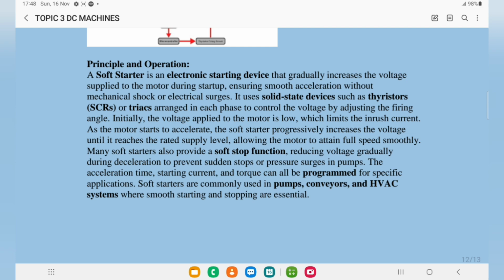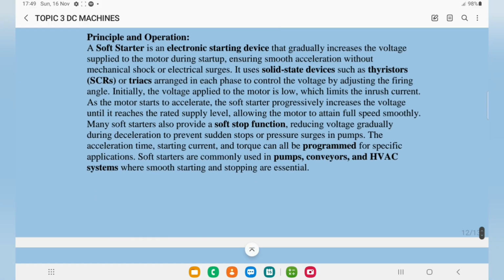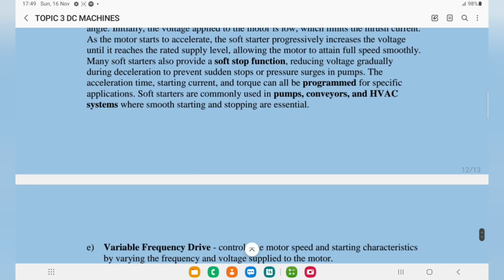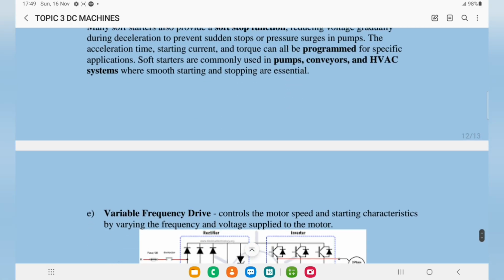Many soft starters also provide a soft stop function, reducing voltage gradually during deceleration. The acceleration time, starting current, and torque can all be programmed for a specific application. Soft starters are commonly used in pumps, conveyors, and HVAC systems, where smooth starting and stopping are essential.